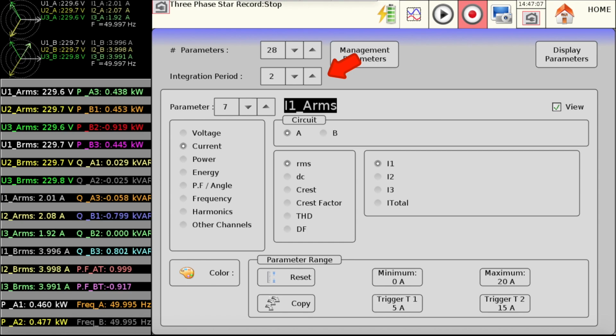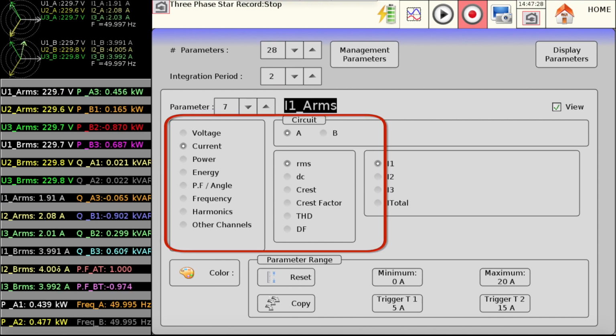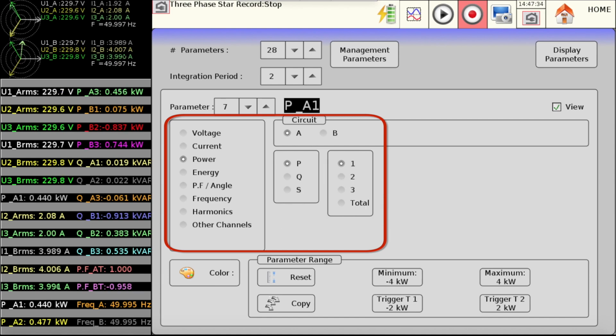Determine the number of integration periods, which means the number of periods that will be taken to calculate the frequency, RMS values, or the power, for example. Select below the parameters you wish to modify. In our case, parameter number 7 is selected. For example, we can modify it to display a total reactive power on our circuit A.